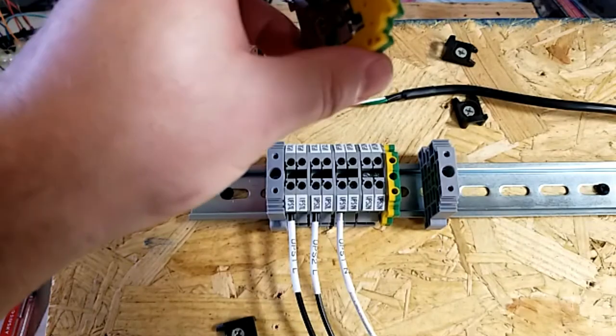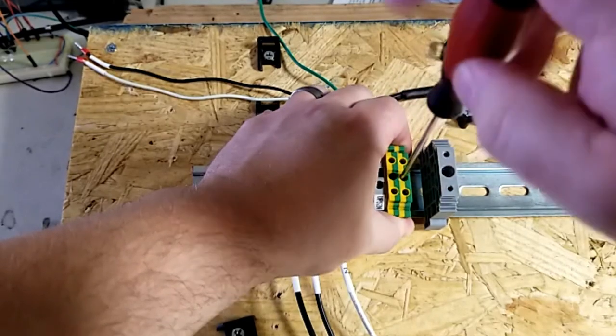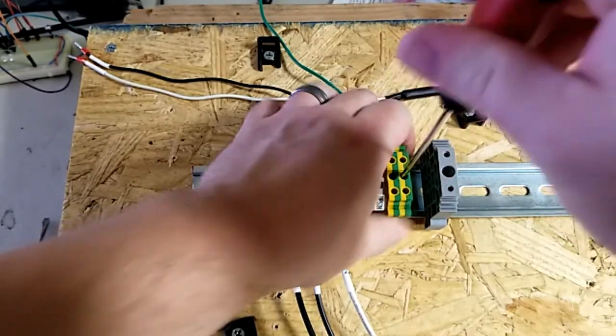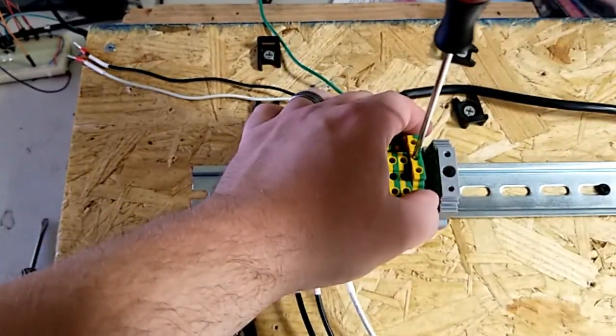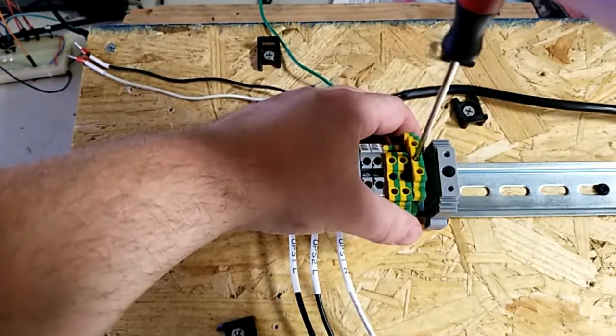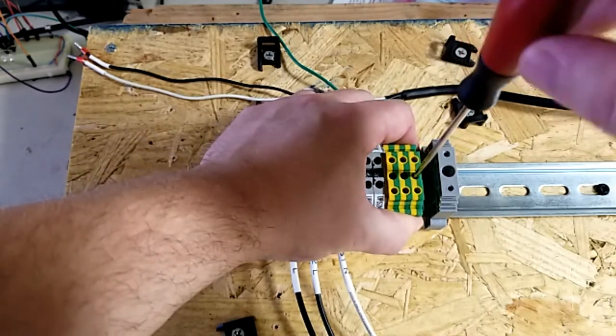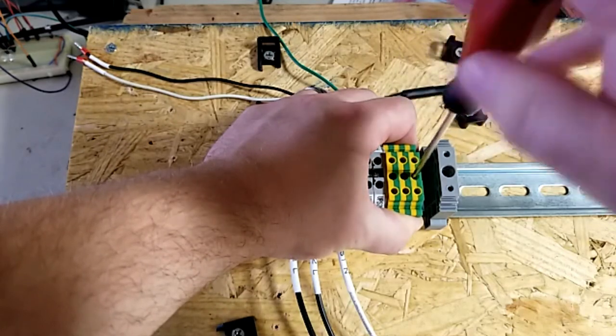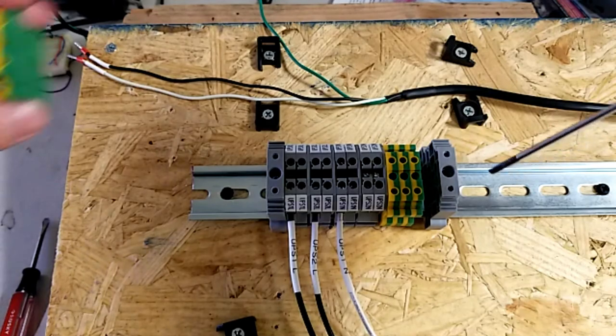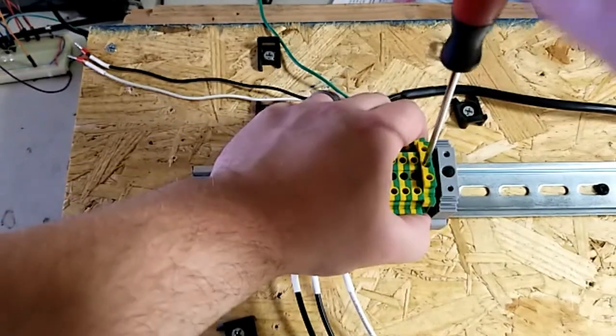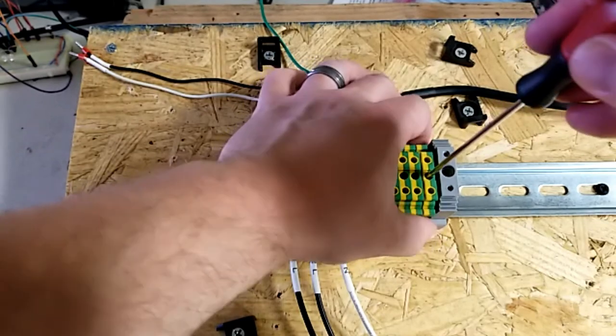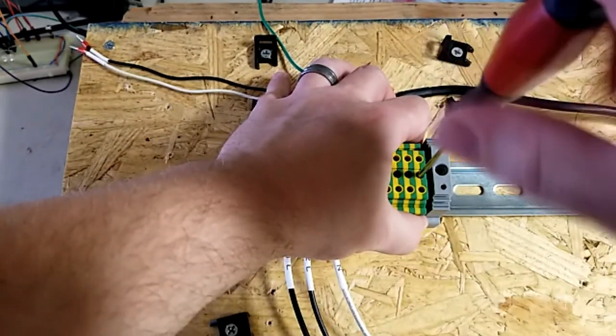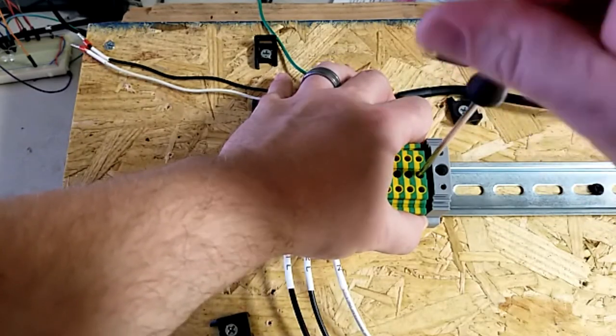So we're going to install the remainder of these. Again, when I clip these on here, if it doesn't go all the way down, I'm going to loosen this screw terminal first. And then that should allow it to go all the way down. Then I will tighten the screw up and that will hold it in place. And when you put these in, what I'm doing also, I'm also pulling these over tight so that they're up tight close to each other. That helps hold them all together nice and firm as well if you squeeze them in tight.